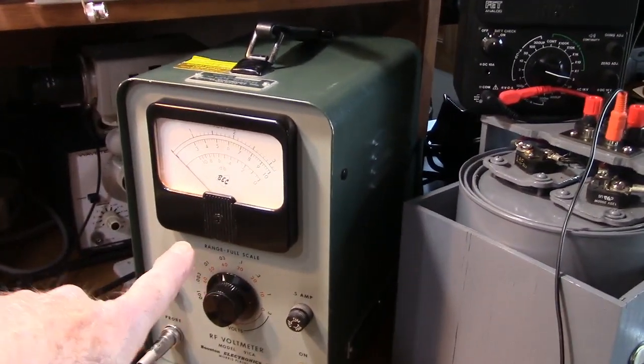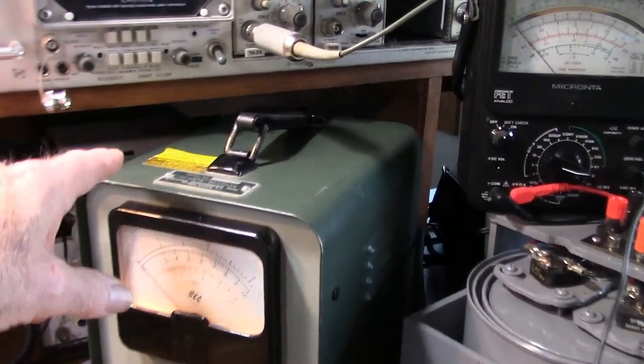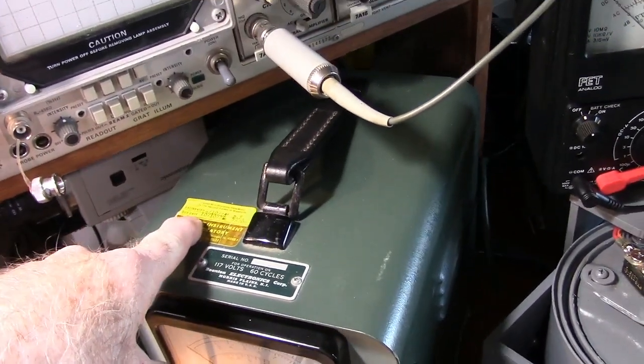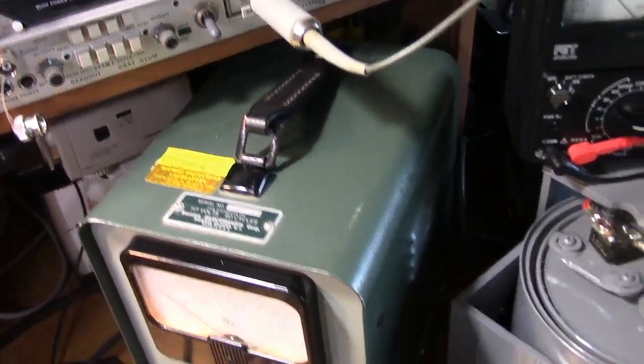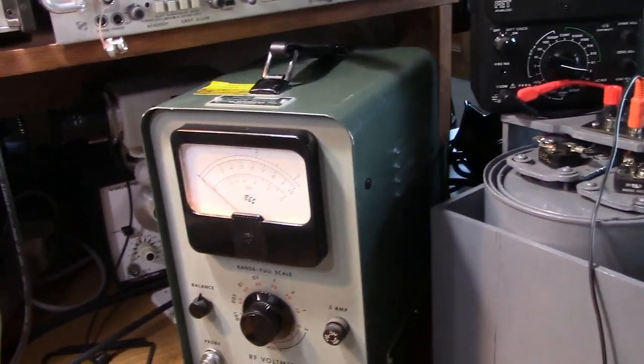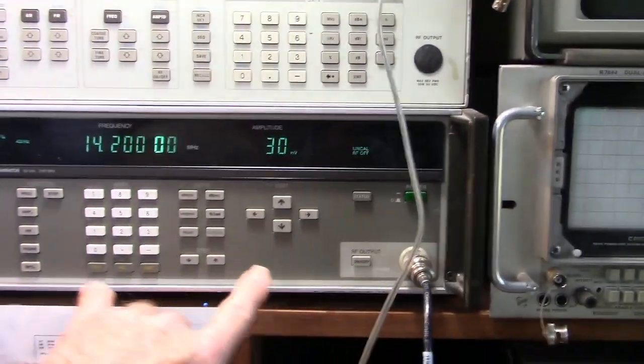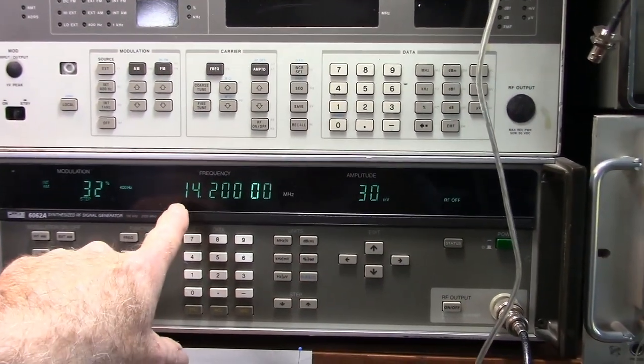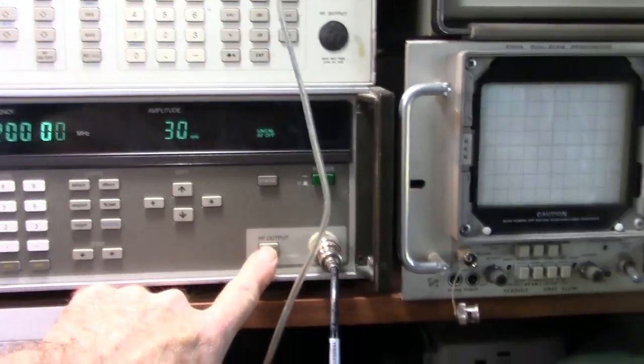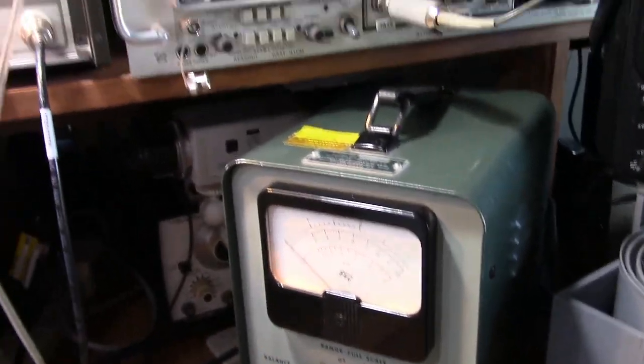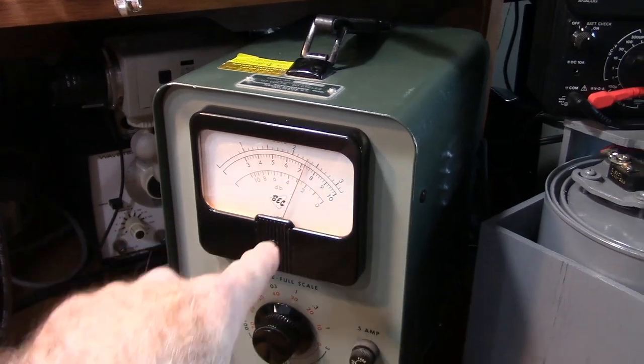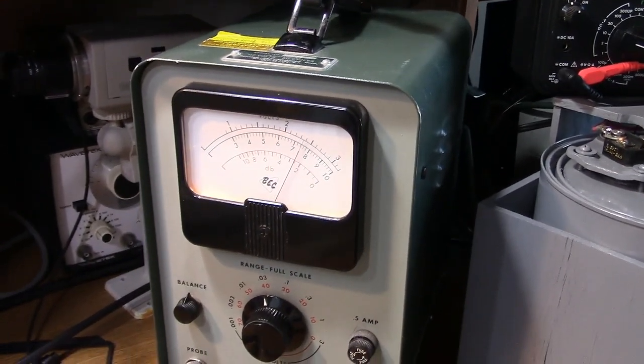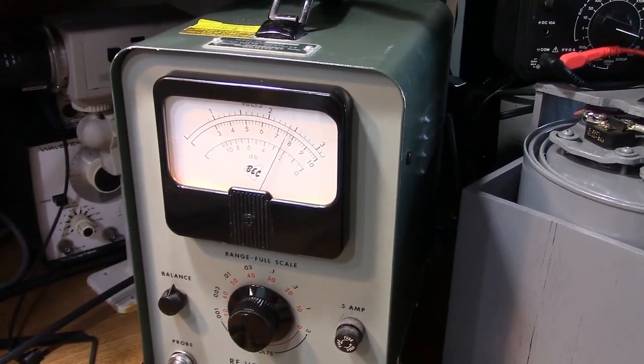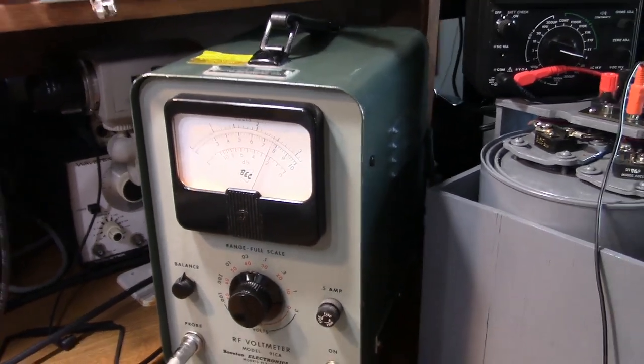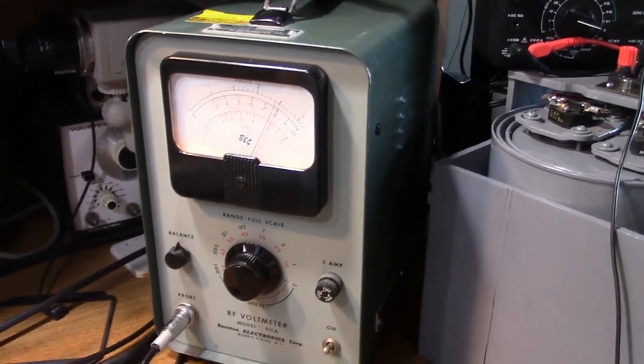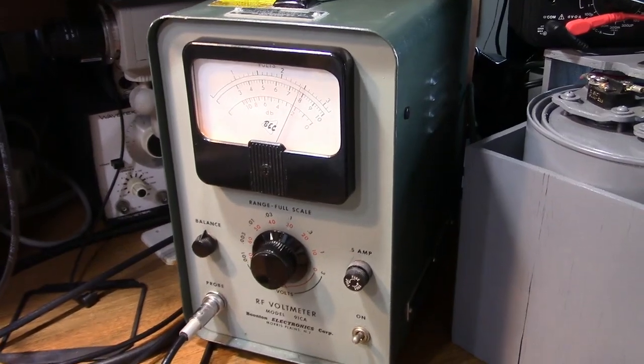This RF voltmeter is out of calibration. There's a calibration sticker showing it was due in October 1978, so it's obviously out of calibration. When I connect a 14.2 megahertz, 30 millivolt signal, I'm measuring just under maybe 24 millivolts, so I'm off by about 6 millivolts. But I'm going to use this basically as a relative indication; I'm not too concerned about it.